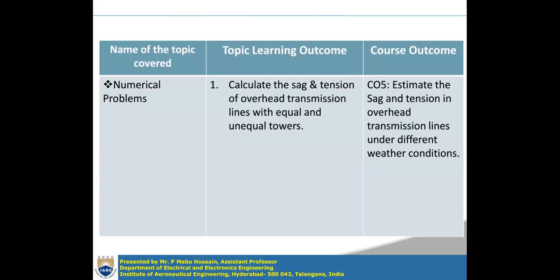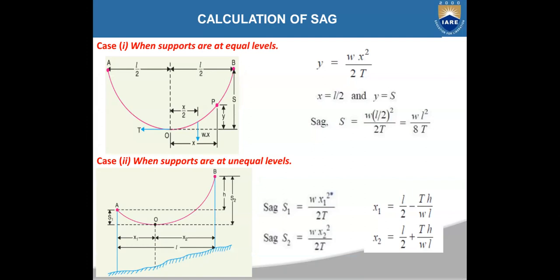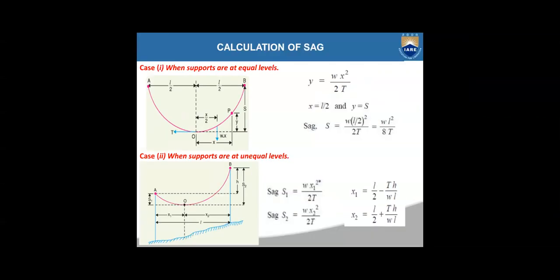For completion of this lecture, you can calculate the sag and tension for your overhead transmission line with equal or unequal towers. For calculating the sag, you have to remember some formulas. When the supports are at equal levels, sag at any point P is given by y = wx²/2T. If you want to calculate the sag from support A or B, then sag S = wL²/8T for equal level supports.